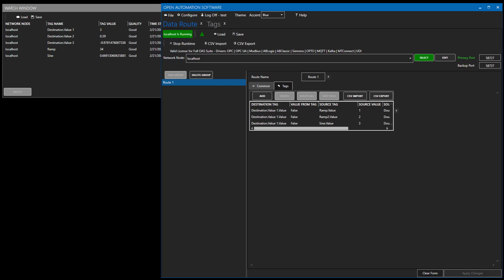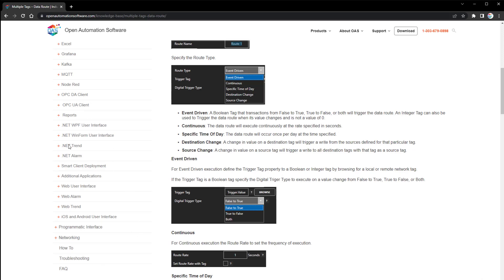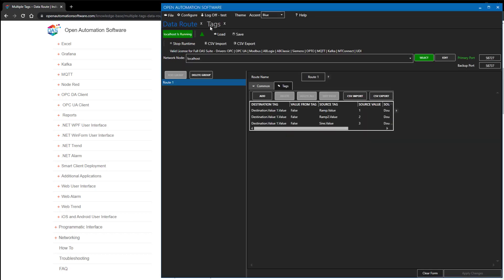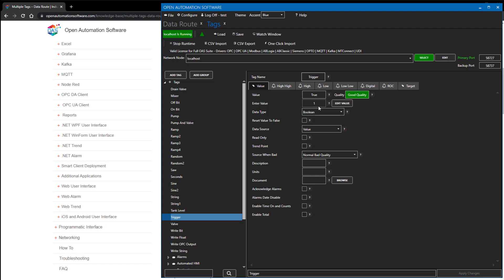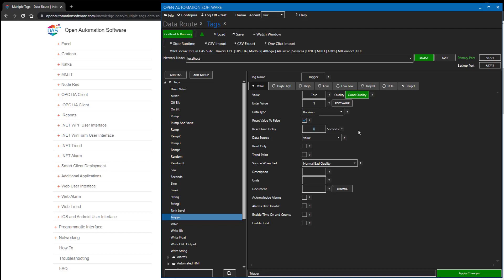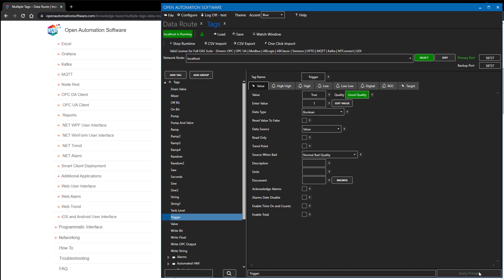There's one other handy feature — using a time on or time off condition. We've been asked many times: how do you reset a Boolean tag with a time delay? For a built-in option on a Boolean tag, there is a reset to false variable where you can put in a time delay — useful if a PLC turns a bit on and after the time delay it resets back to false. For a time off condition, that can be accomplished using the data route feature.